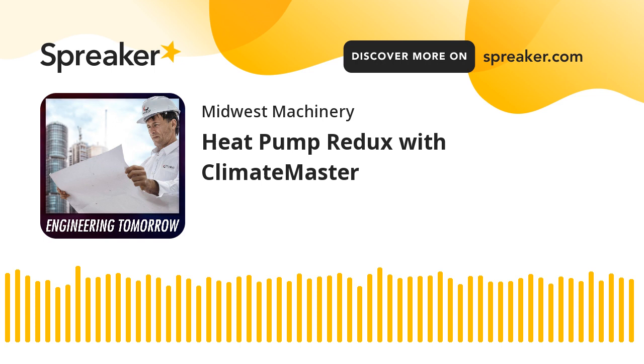Other component is the loop piping. This loop piping is what carries water to and from the heat pumps and connects the individual components of the system. Piping can be a traditional two-pipe system or a single-pipe system, as I mentioned. Careful planning of this water pipe is important, as it is about 25 to 35% of the installation cost of the system. Two-pipe systems can be arranged in a direct return configuration or a reverse return configuration.